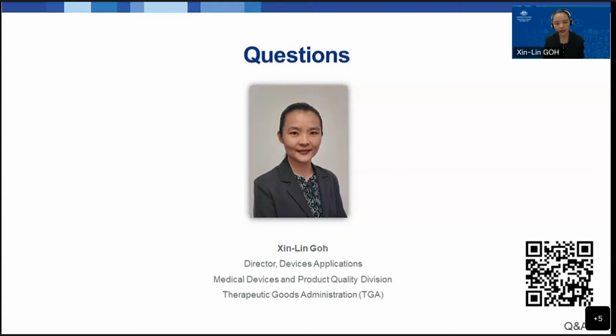If that is the case, as outlined in earlier examples, a sponsor can apply for a manufacturer evidence variation to update their MDD on file to the MDSAP. Alternatively, if they still require the MDD to be linked or associated with certain ARTG entries, they can launch a new manufacturer evidence application for their MDSAP and then delink and relink the ARTG entry for the MD to be associated with the MDSAP certification.